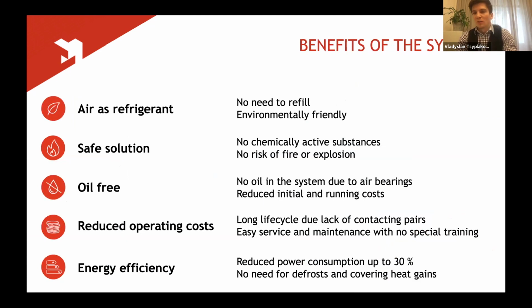So the benefits of our systems, number one is the fact that we use air as the refrigerant. You don't need to refill it and it's environmentally friendly. So coming to the ultra low temperatures, if we were talking about a temperature of -80, for example, with air, we're substituting two extremely harmful refrigerants, for example, R404A and R23. R404A has about 4,000 GWP and R23 has around 15,000 GWP. So as you can see, to substitute those huge values with zero is a big feat.